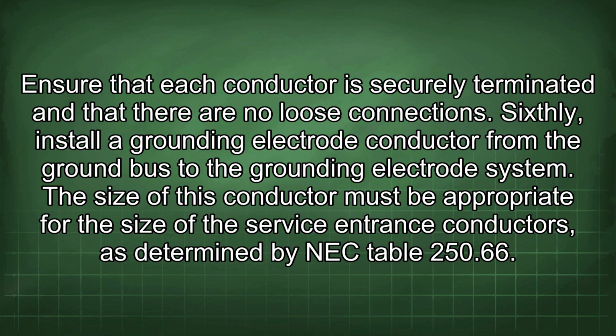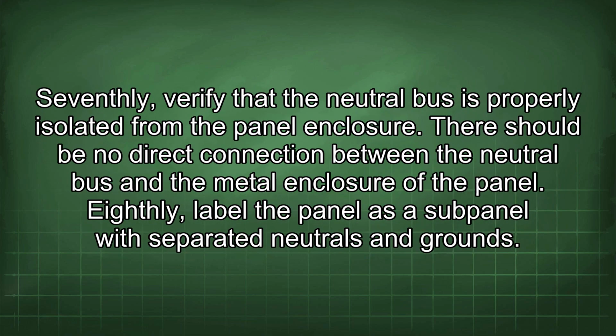Ensure that each conductor is securely terminated and that there are no loose connections. Sixthly, install a grounding electrode conductor from the ground bus to the grounding electrode system. The size of this conductor must be appropriate for the size of the service entrance conductors, as determined by NEC Table 250.66. Seventhly, verify that the neutral bus is properly isolated from the panel enclosure.